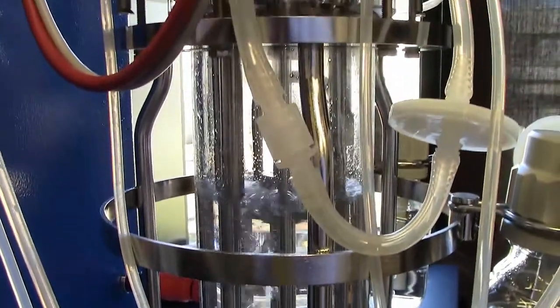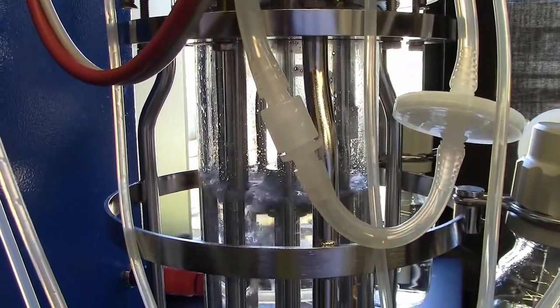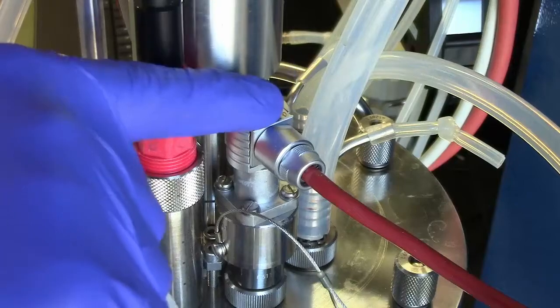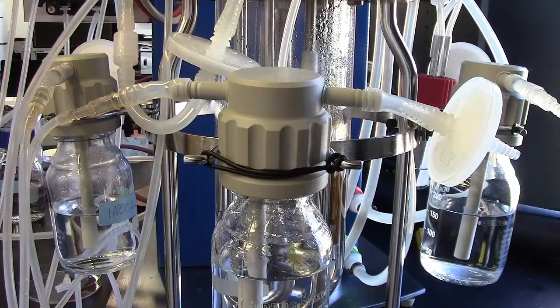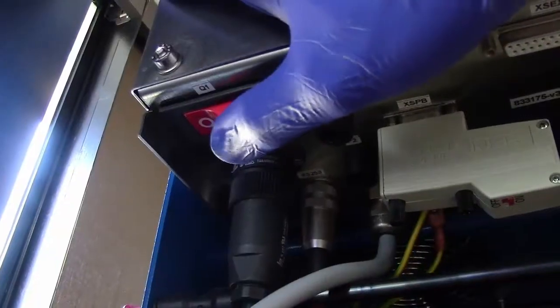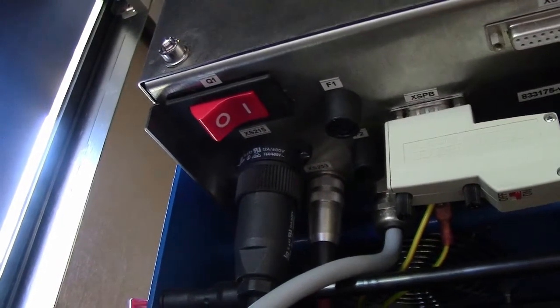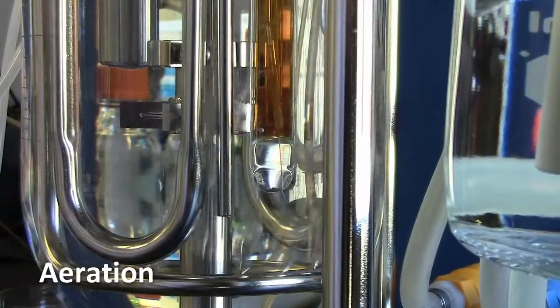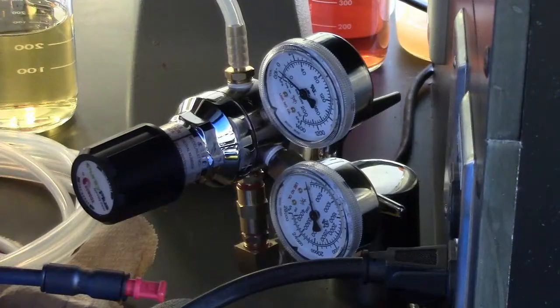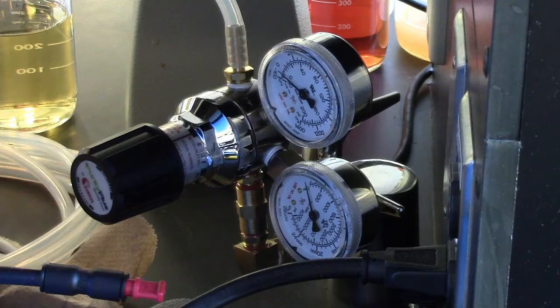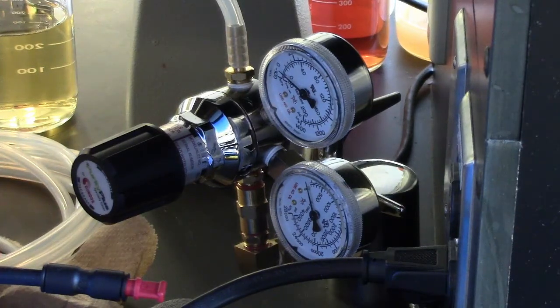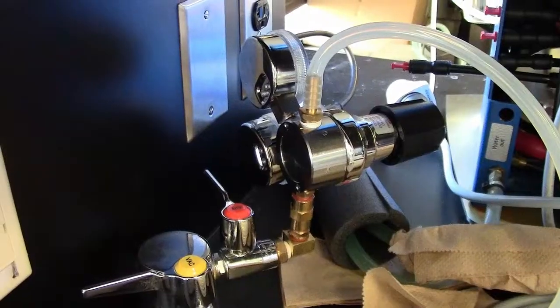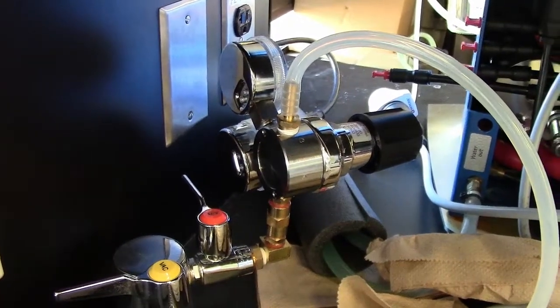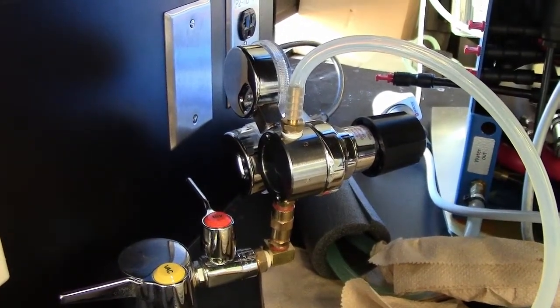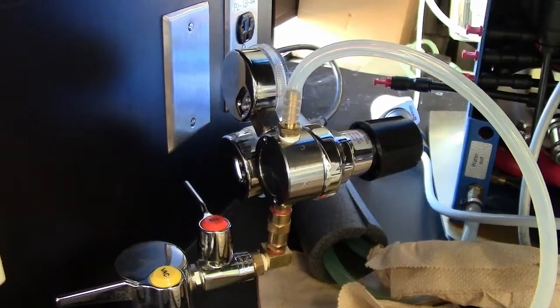The bioreactor can be roughly divided into 5 main subsystems: aeration, temperature control, addition and transfer, the fermentation vessel, and the control unit. Let's start with aeration. We've connected our regulator to a benchtop air valve for air supply, though this assembly can be reconfigured for air canisters as required. The regulator prevents the system from taking the full pressure of the building's air supply, which would cause damage to the machine.